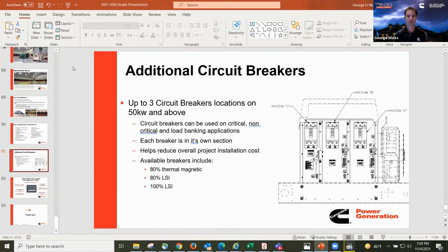Oh yeah. I don't know how many faults there are, but there are so many sensors monitoring temperatures, frequencies, and voltages coming in and out of all the main touch points on the gen set. So it's speed too. I think very well protected. Oh yeah, our engine RPM protections are incredible. The guys say even the circuit breakers are almost redundant, not even needed on these newer machines. The computer is going to take over before the breaker mechanically trips.